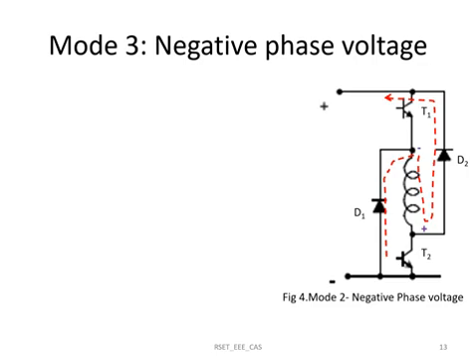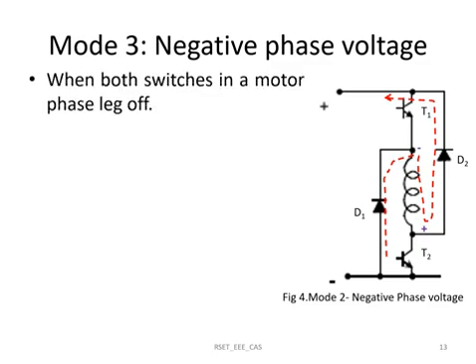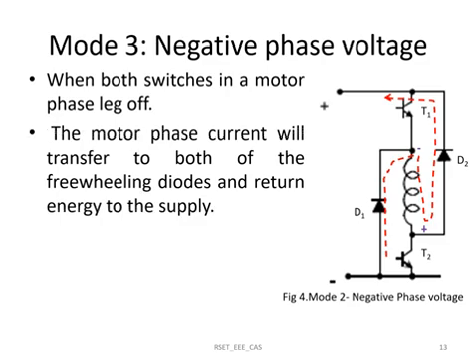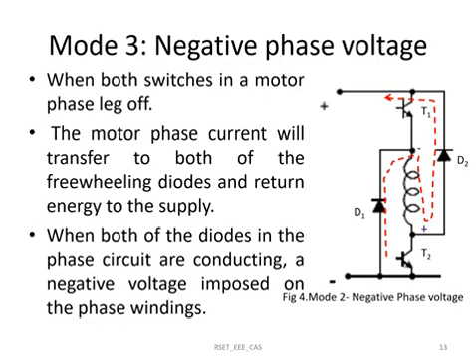In mode 3 (negative phase voltage), both switches T1 and T2 are turned off. The energy stored in the winding during mode 1 is fed back to the supply through diodes D1 and D2, and a negative phase voltage is imposed on the winding. The lower terminal of the winding has positive polarity and the upper terminal has negative polarity, which is why it is called negative phase voltage mode.